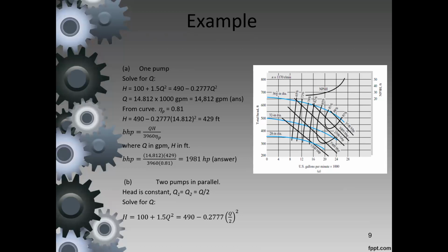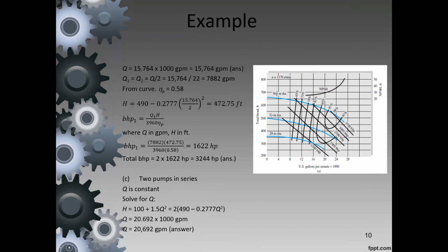Ito yung system. Ito yung pump, yung head ng pump. Okay? Bakit hindi divide-divide to? Sa system to eh. I-equate mo lang yung head ng pump. So Q is equal to 15.764 times 1,000 GPM is 15,764 GPM. Ito yung answer mo. So Q1 is equal to Q2 is equal to Q over 2 is 15,764 over 2 is 7,882 GPM. From the curve, 0.58.